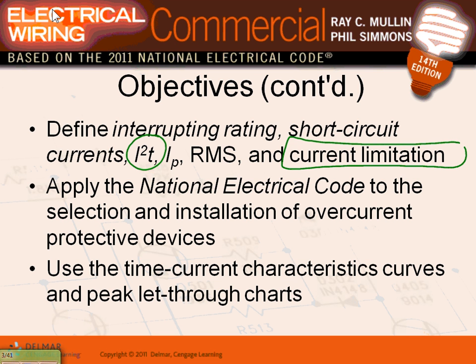The most important thing about current limiting fuses, as we can see, guys, is if I have 100,000 amps coming in, and my machine here is rated for, say, 85, right? What happens if you put a current limiting fuse on this machine, it'll take the 100,000 amps and knock it down to 80 amps just by going through this material. They call them current limiting fuses. Because of them, we can have a lot of major machines, guys. Otherwise, current limiting fuses are a major, major part of what we do.